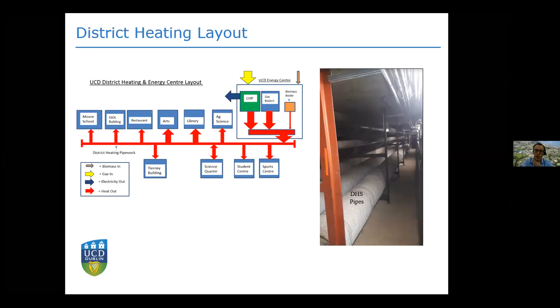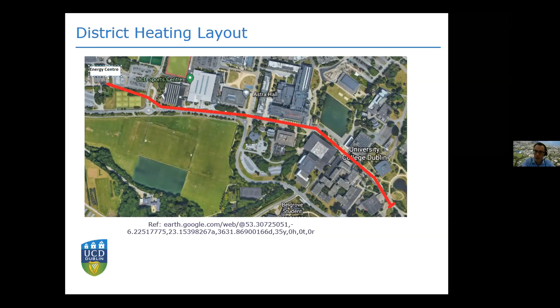Those pipes are the district heating pipes, 12-inch pipes side by side. So geographically, that's what it looks like - our energy center to the left of the picture is up near, if anyone knows UCD, near the water tower. The duct runs more or less down through the center of the campus, with subways into the plant room in most buildings. That's great in terms of access and maintainability. To the right of the picture we have one or two new buildings which use direct buried pipework connecting to the heating system.